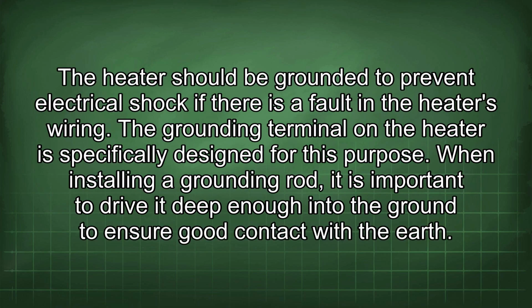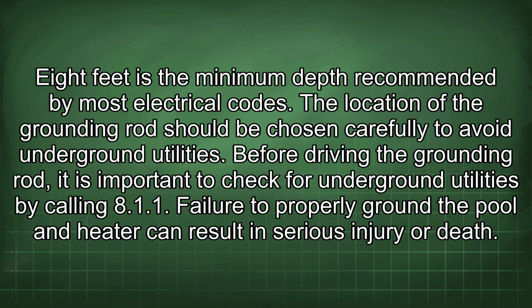The heater should be grounded to prevent electrical shock if there is a fault in the heater's wiring. The grounding terminal on the heater is specifically designed for this purpose. When installing a grounding rod, it is important to drive it deep enough into the ground to ensure good contact with the earth. 8 feet is the minimum depth recommended by most electrical codes. The location of the grounding rod should be chosen carefully to avoid underground utilities. Before driving the grounding rod, it is important to check for underground utilities by calling 811.